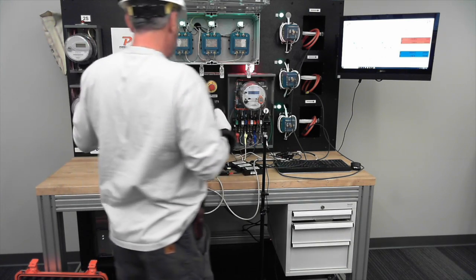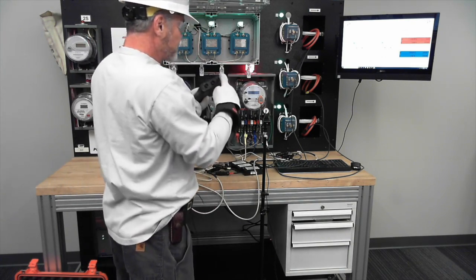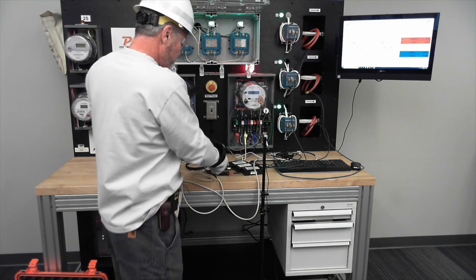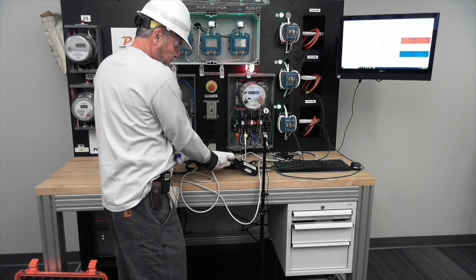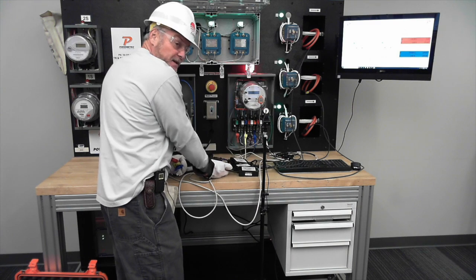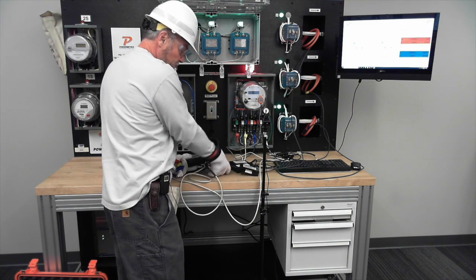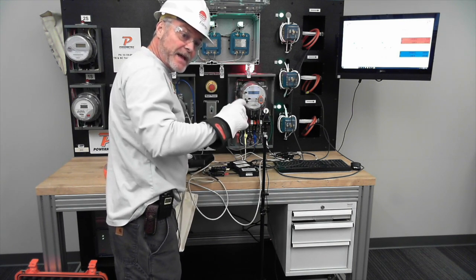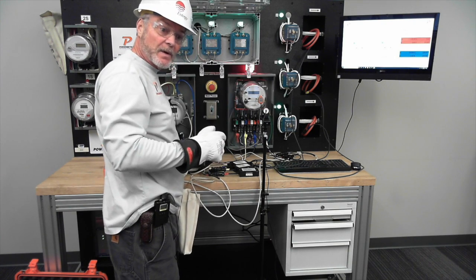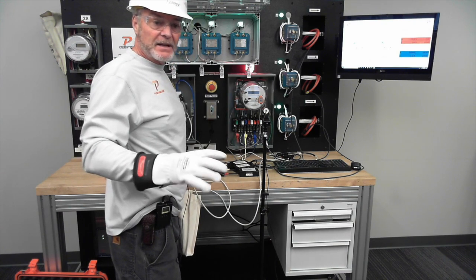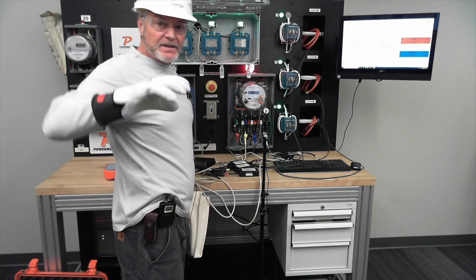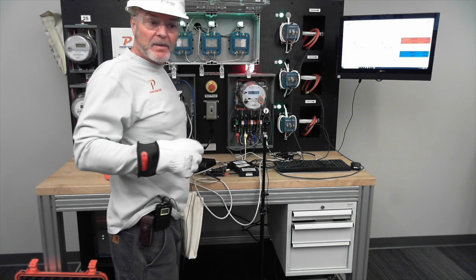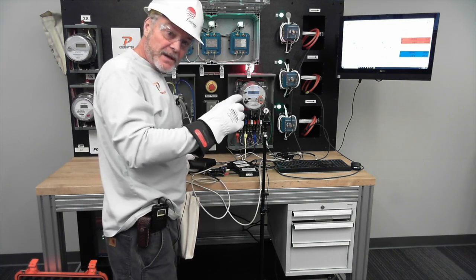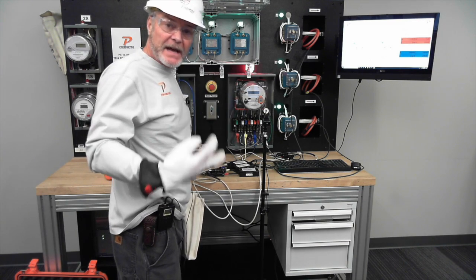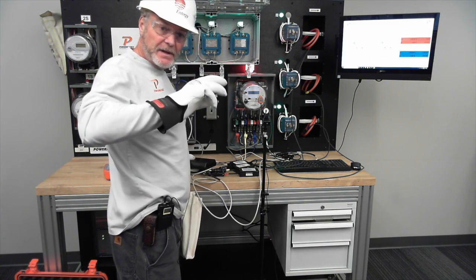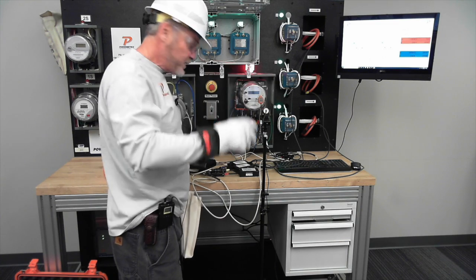For PTs, when we make the connections, it just connects in. These are the standard connections you see on the ends of these probes, our same pinned connectors, and they're milled so once you turn it you'll feel it drop down, then you tighten it to line the pins up correctly. I know that's a silly little thing, but I've seen guys just grab and start twisting and cramming them in. You're going to feel it drop in, because otherwise you're not lining the pins up and you'll jack that connector up. So you feel it, turn it, and when it drops in, then tighten it up.